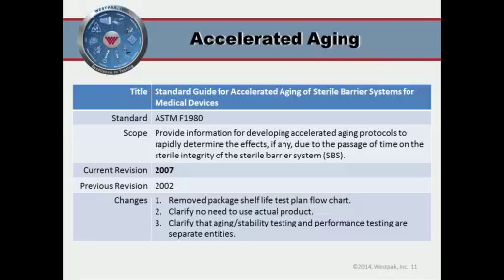And Herb would like to go over accelerated aging. It's important to note, Katie, that the process of accelerated aging is based on the Arrhenius equation, which many of you are familiar with, I'm sure. It states briefly that the molecular activity in an organic molecule will approximately double with every 10 degrees C rise in ambient temperature. So the validity or application of this particular equation for acceleration aging of medical devices and other products has been, and likely will be for some time in the future, hotly debated. It is, however, acceptable for FDA submission when combined with real-time aging to validate the accelerated aging process in smaller increments. And we're going to talk about those in general.